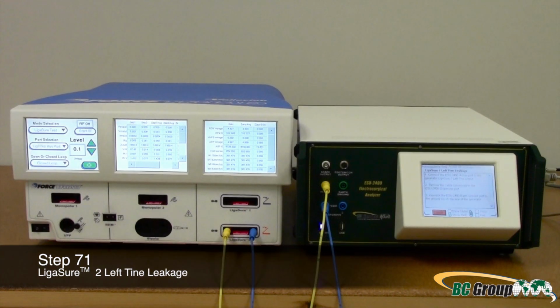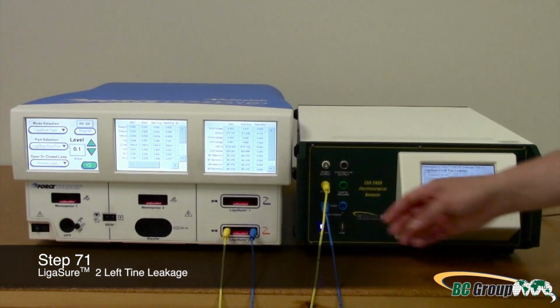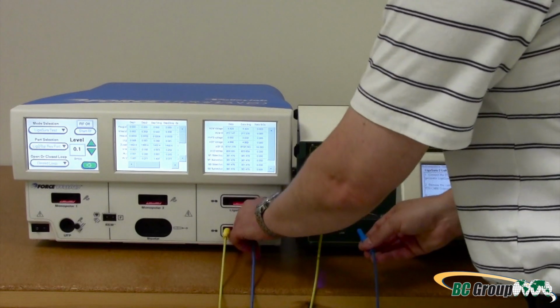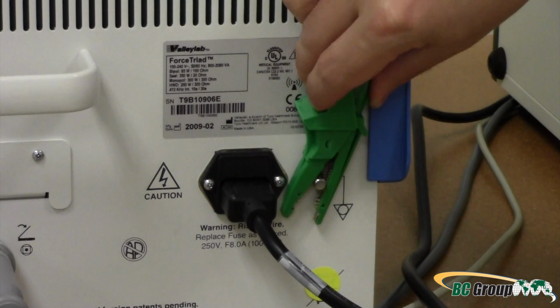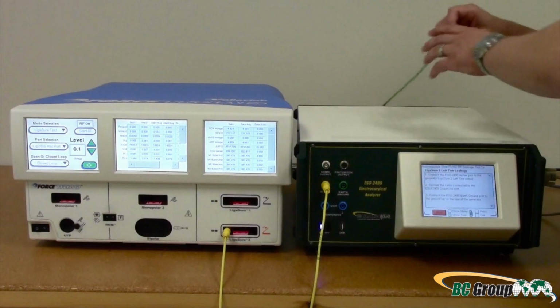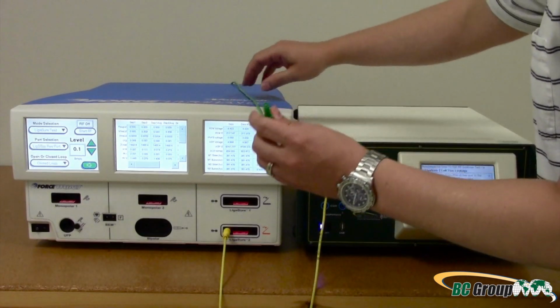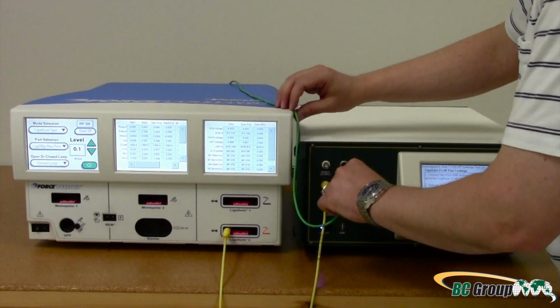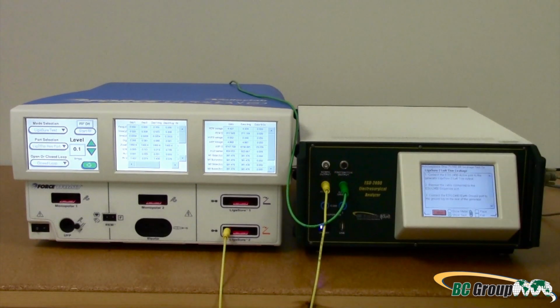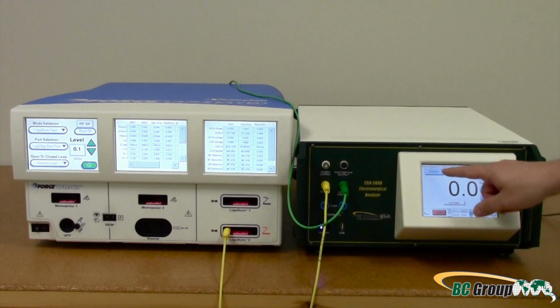Leakage testing. Step 71. LigaSure 2 left tine leakage. Remove the cable connected to the ESU-2400 dispersive port. Connect the ground lug on the rear of the generator to the ESU-2400 earth ground port. Select Show Meter and then press Capture.